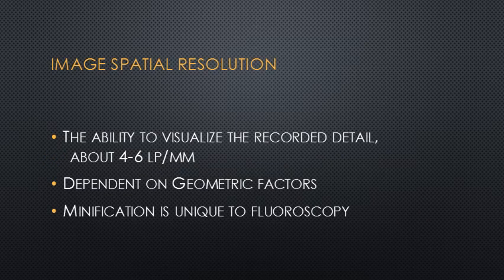To see really small details on the dynamic image, geometry becomes very important — for the same basic reasons as static imaging, but with differences in fluoroscopy. One of these is minification gain. Spatial resolution is dependent on the video monitor display, but due to processes such as magnification, motion, and the light phosphor penumbra, the ability to see detail can be degraded at the display monitor itself.